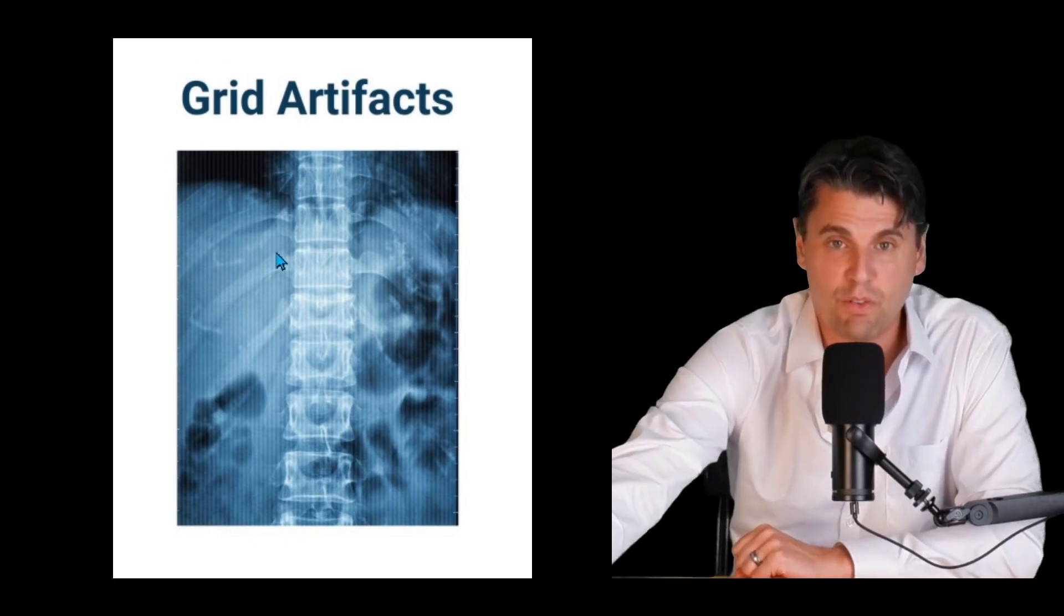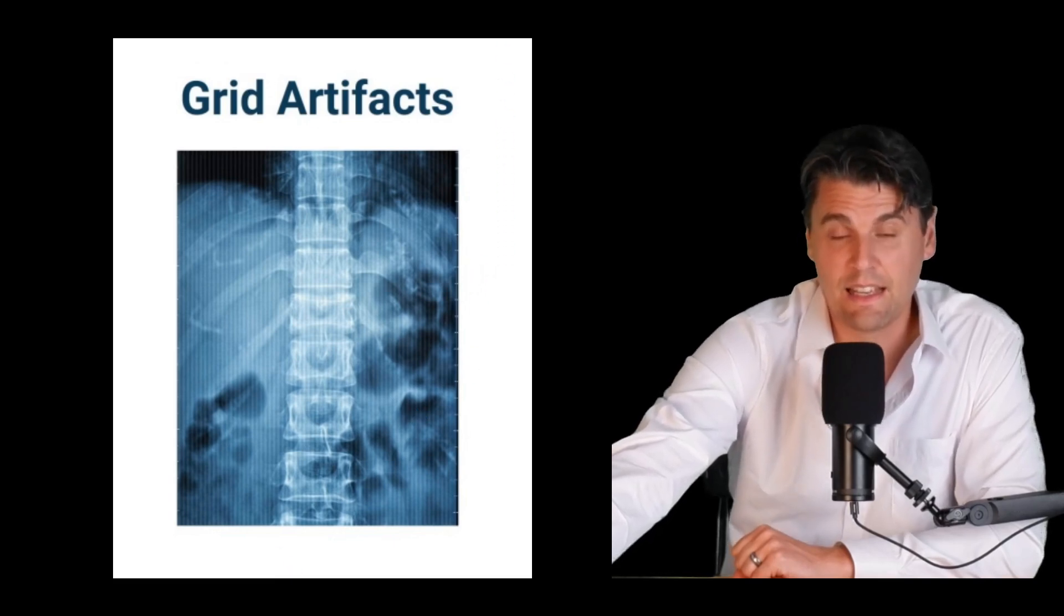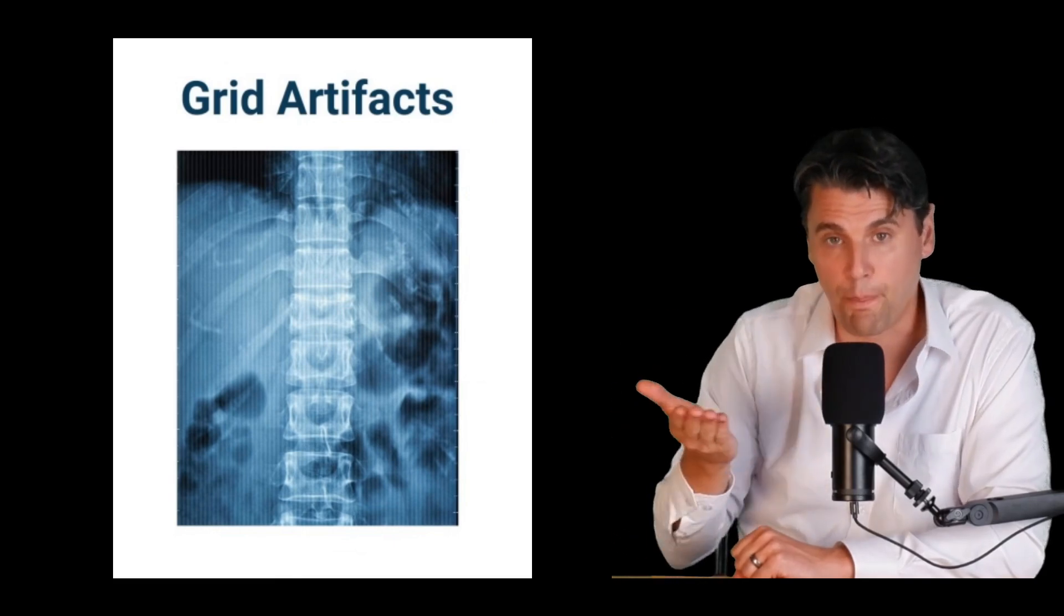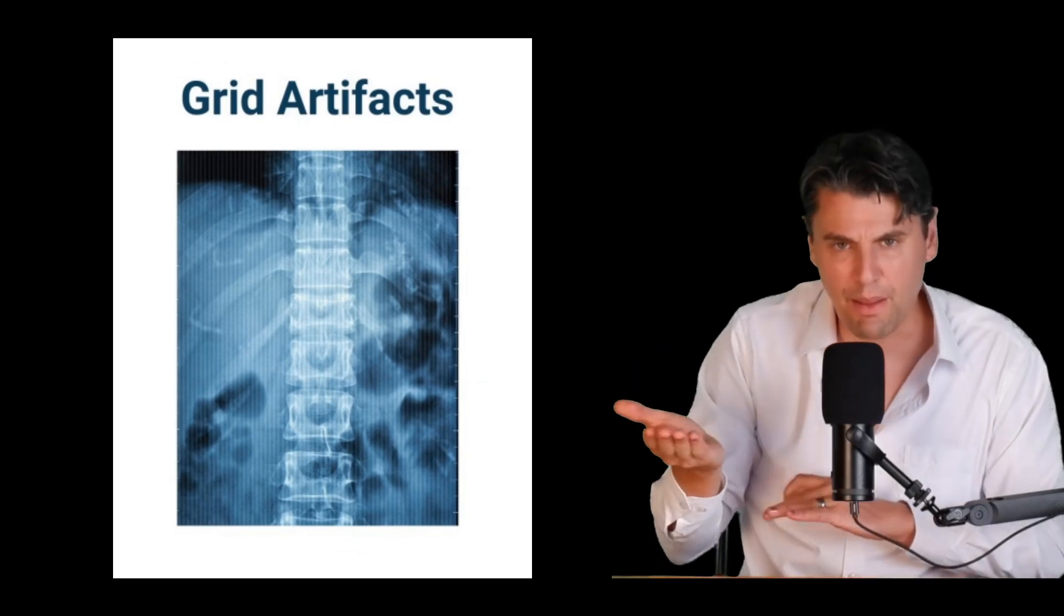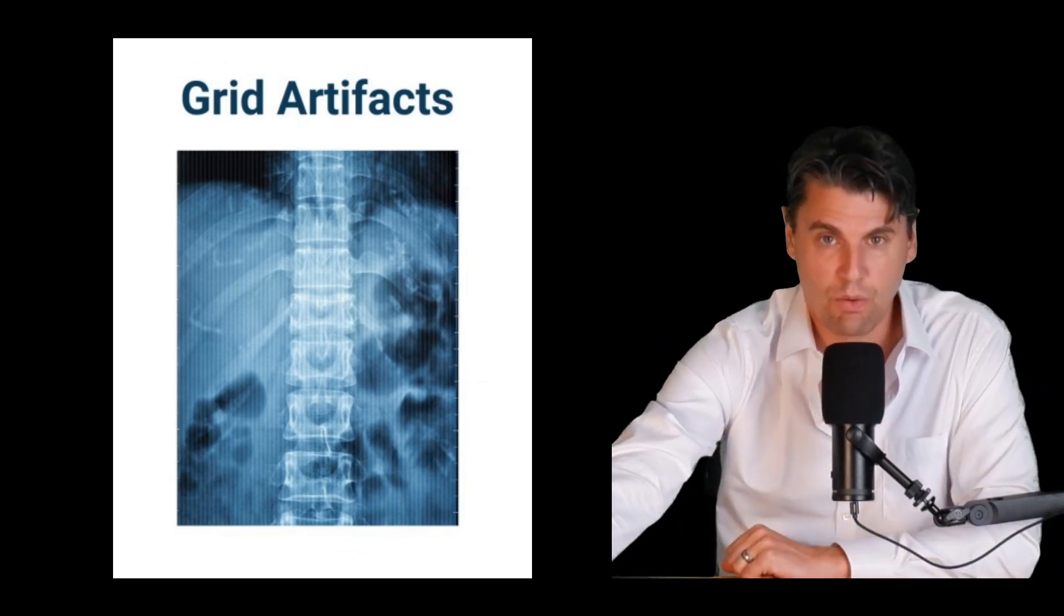Another thing you can have is grid artifacts. If you're using an x-ray grid this is an artifact in the up down direction here and if there is not either a software or motion of the grid in order to essentially blur out the grid lines you could get grid lines on your images.